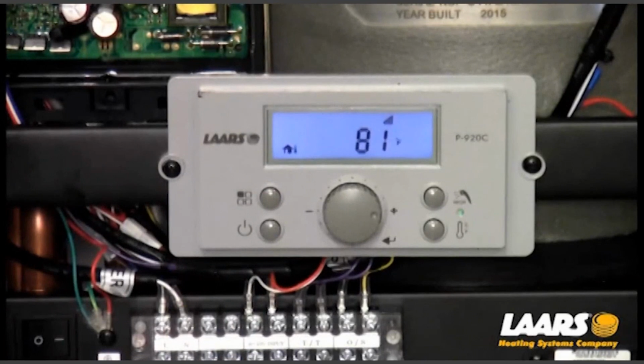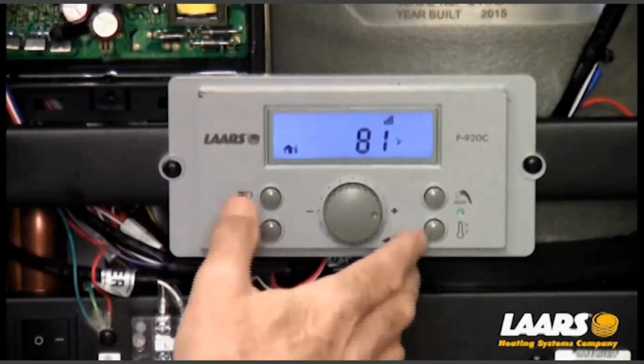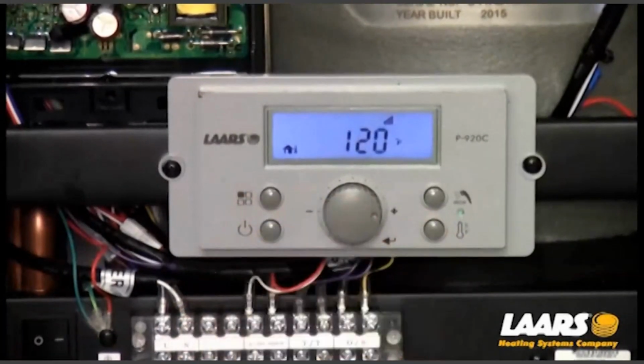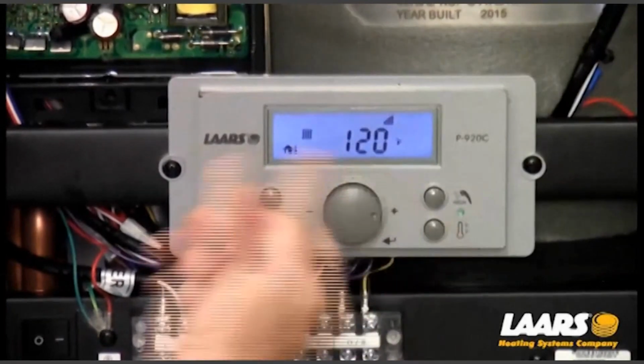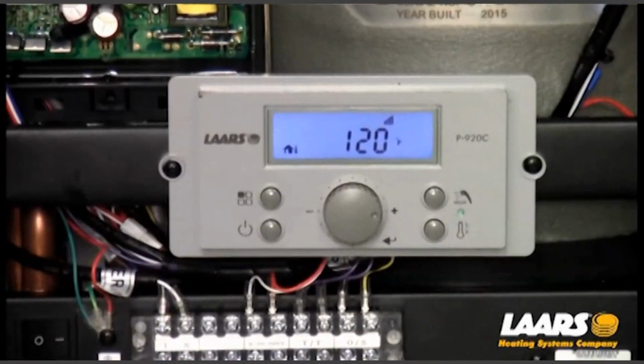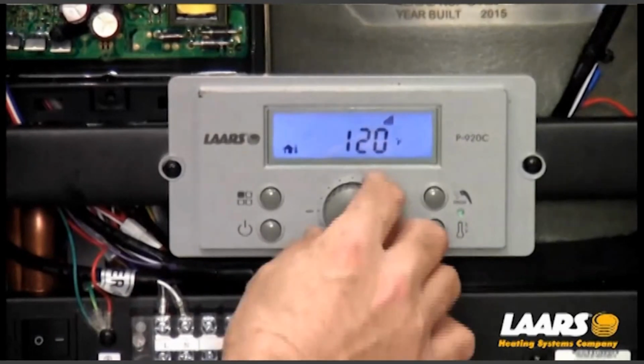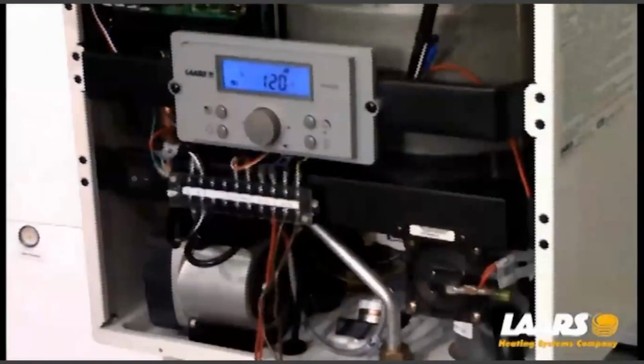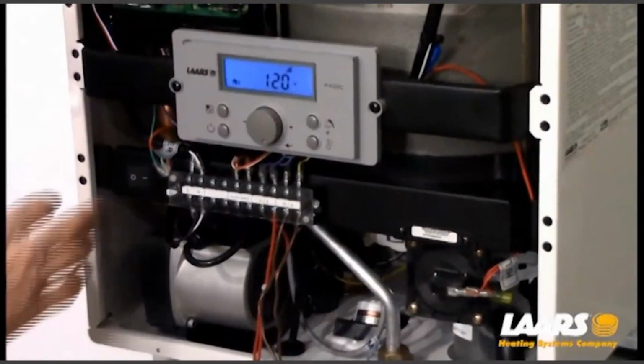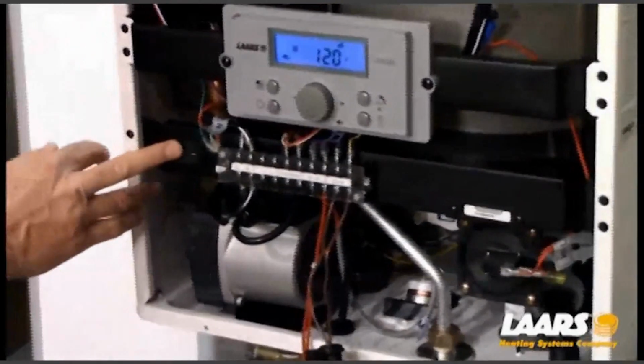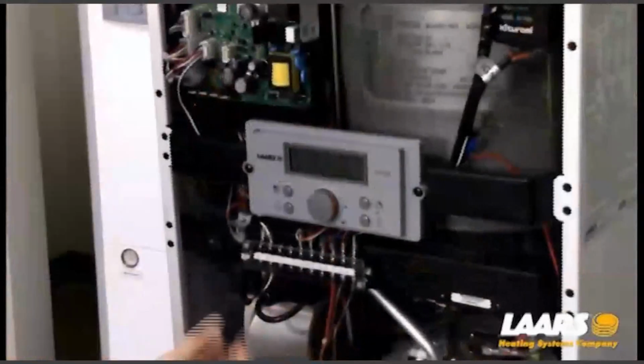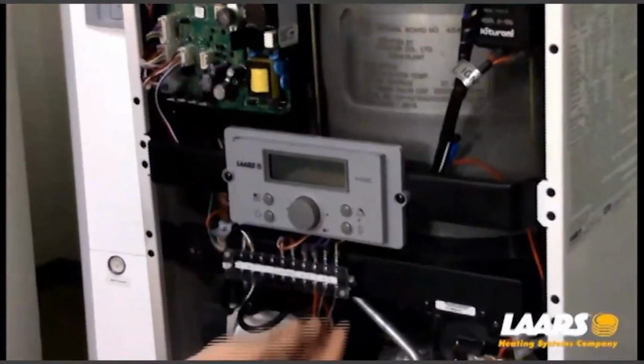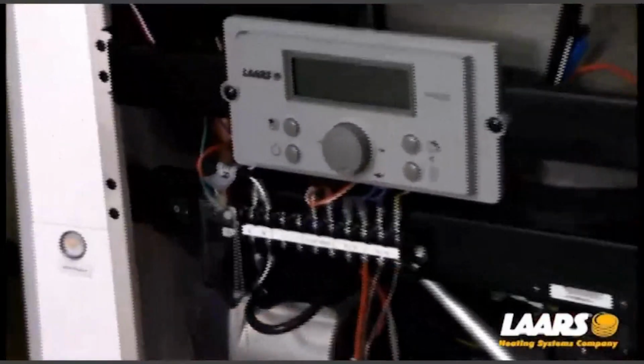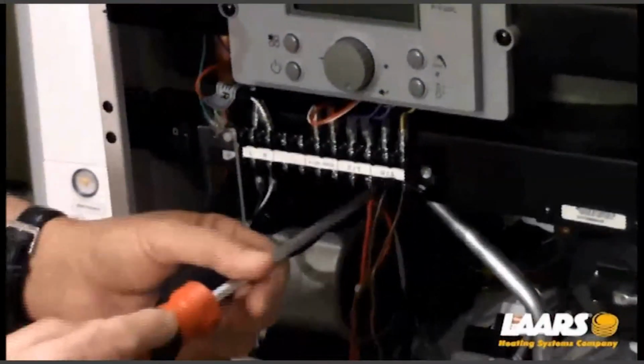The first thing I want to do is remove one of the outdoor sensor wires. The reason is that if we get into setup for central heat, very simply by pressing that symbol, it's showing the defaulted setting of 120 degrees. Well, with the outdoor sensor hooked up, we cannot adjust that set point. So I'm going to power off the display, and I will remove one wire from our outdoor sensor. I'm going to remove the plastic cover here by pulling forward and dropping it down.